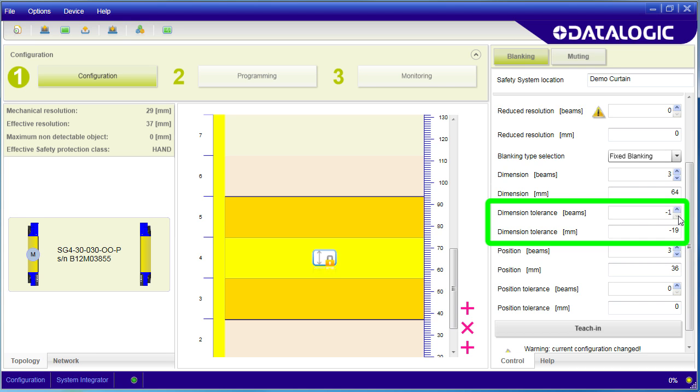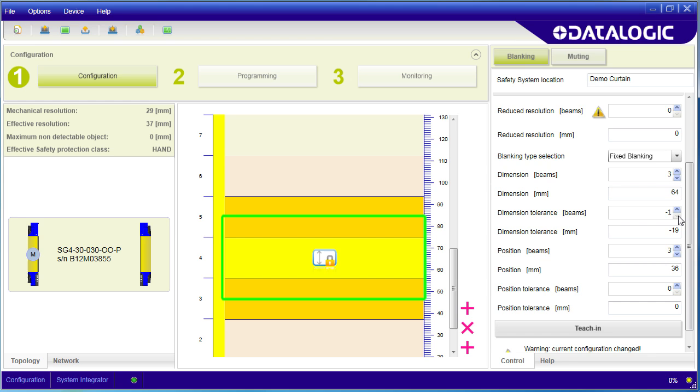Specify that dimension tolerance here. In this case, say you set aside three beams for blanking, but one beam on either side is set aside for variations in the blockage size. This is particularly helpful if you have something blocking part of a beam and vibration is enough to block and unblock that beam.